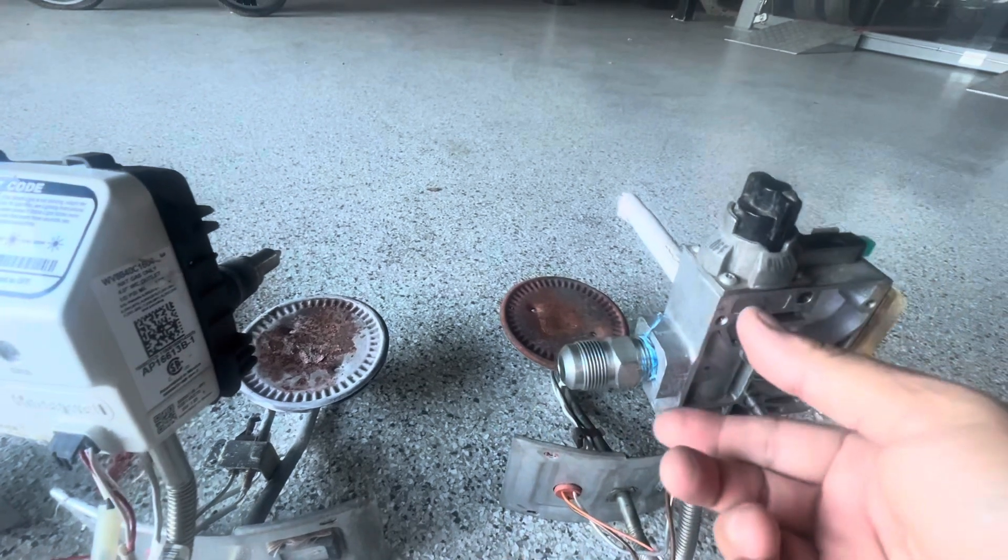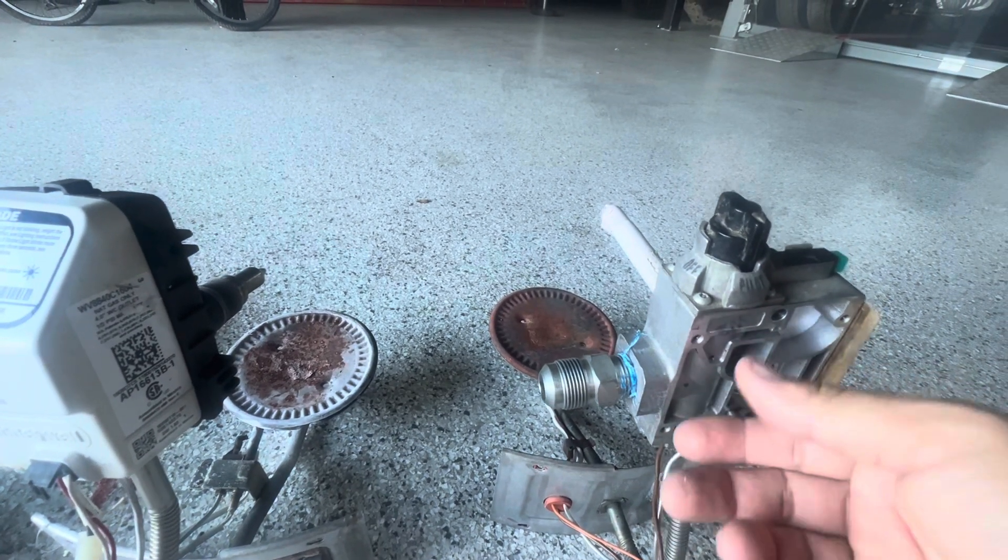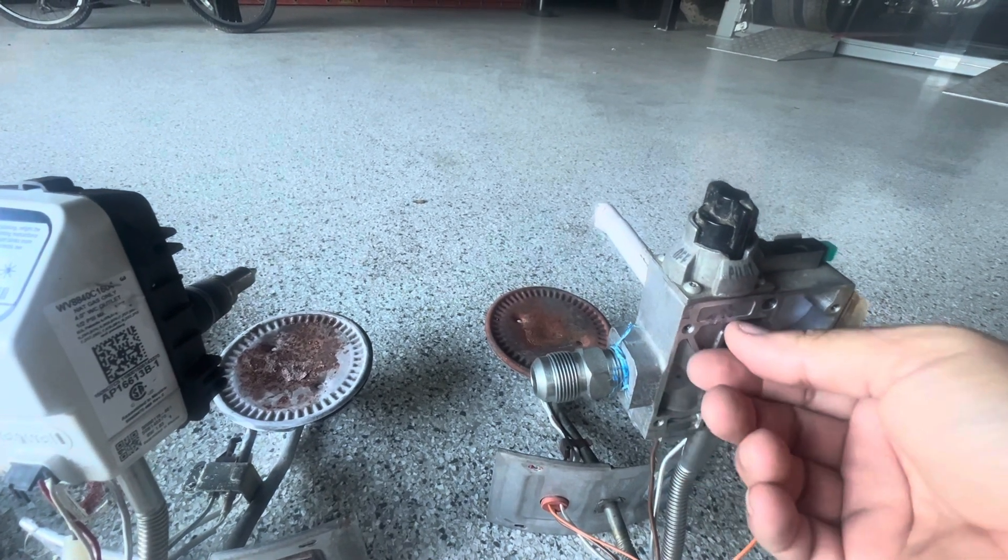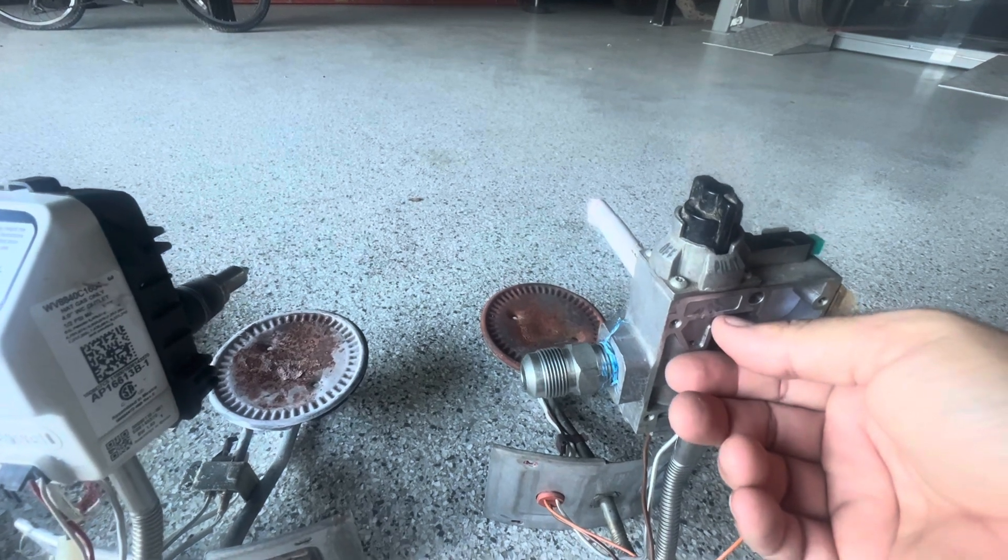Once that's extinguished, the millivolts will drop. So at about five millivolts, that mag assembly will drop back to the closed position and shut all the gas off.